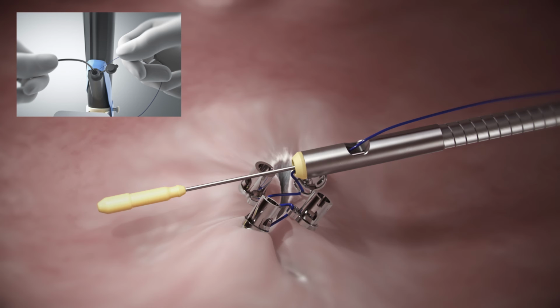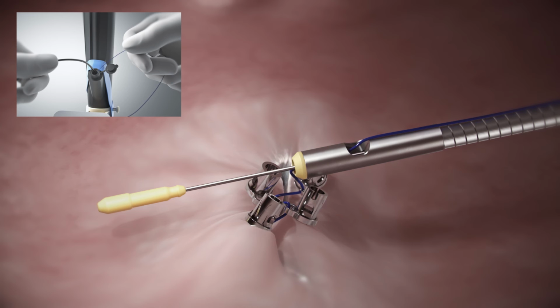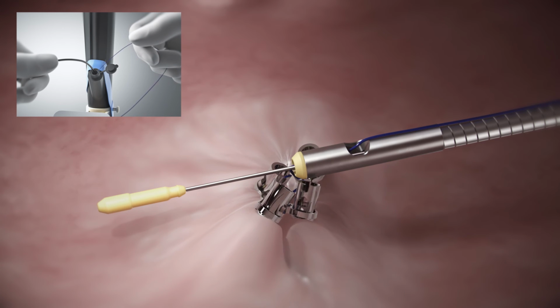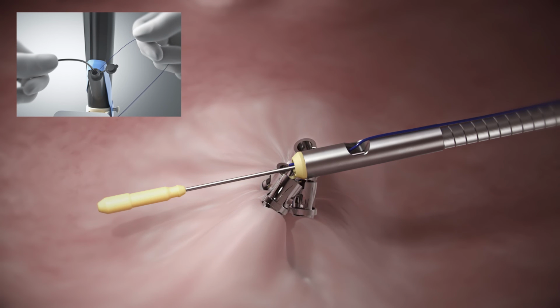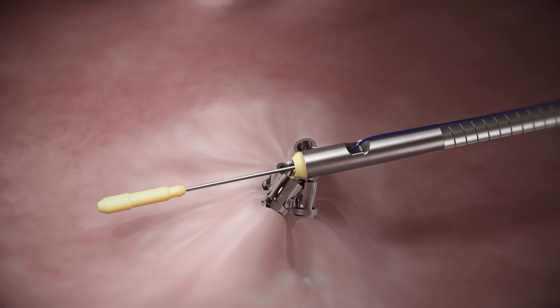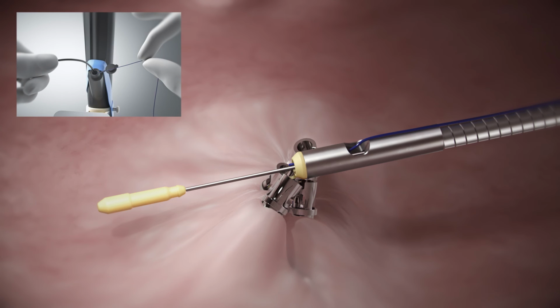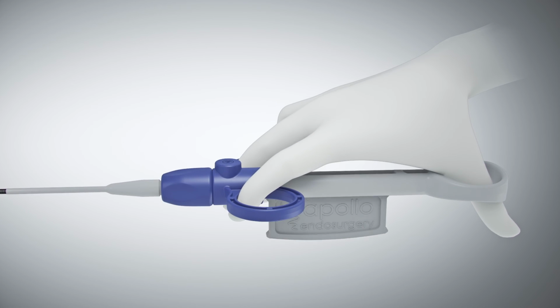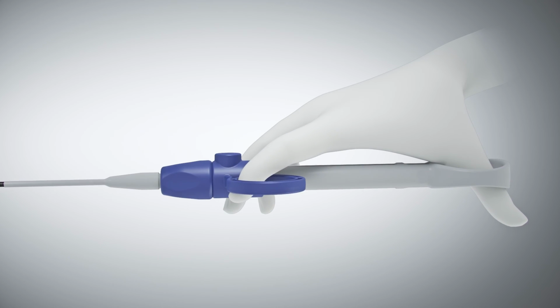While holding the cinch catheter in place, apply tension to the suture until the helix tacks and tissue has been approximated. Care should be taken not to pull suture too tight, resulting in breakage. Prior to deploying the cinch, hold suture tension gently. Grasp between thumb and pointer finger, allowing the suture to slide. Open the cinch handle with the palm facing down. This will release the safety mechanism.